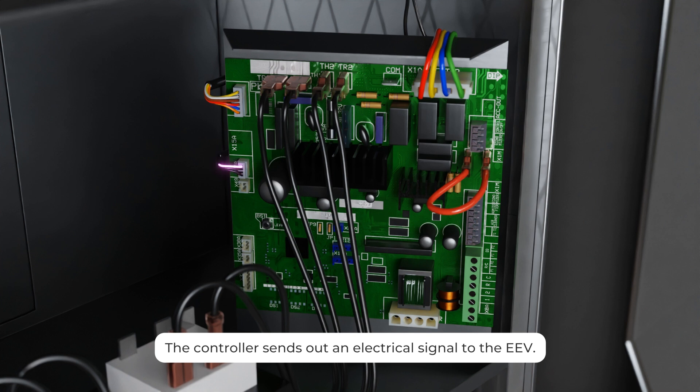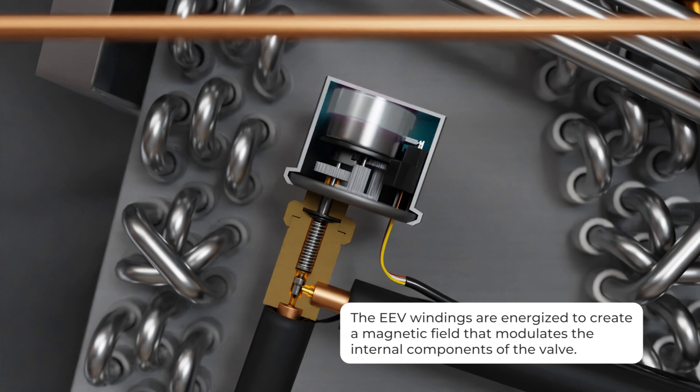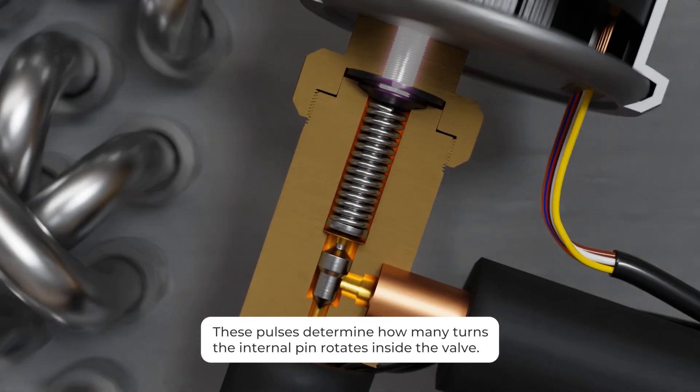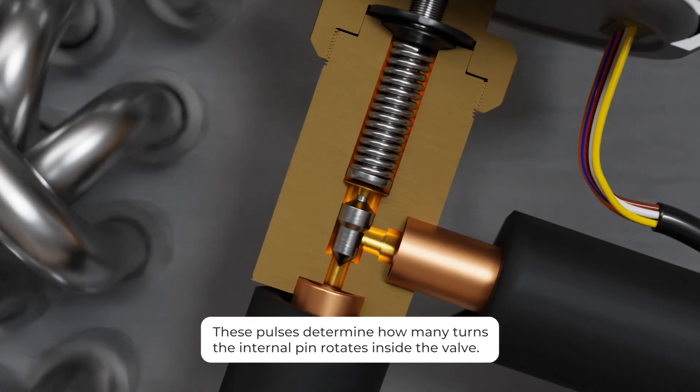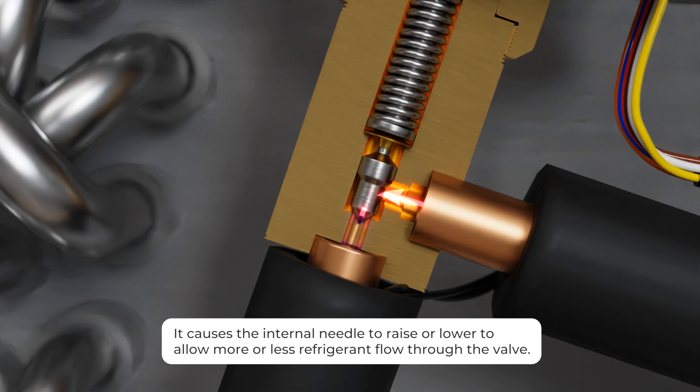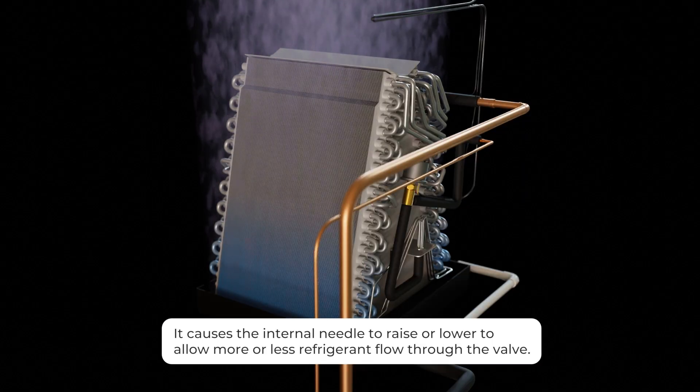The controller sends out an electrical signal to the EEV energizing windings to create a magnetic field that modulates the internal components of the valve. These signals are called pulses. These pulses determine how many turns the internal pin rotates inside the valve causing the internal needle to raise or lower to allow more or less refrigerant flow through the valve.